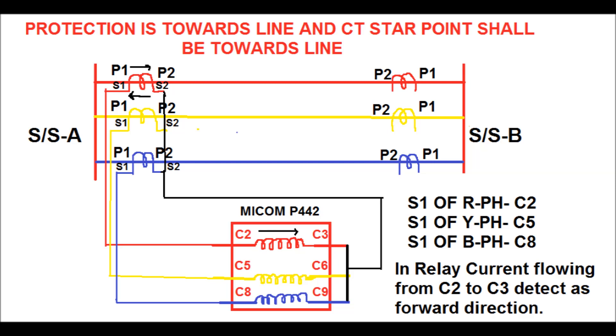For reverse polarity, we can change the polarity either in the primary side or in the secondary side. In the primary side, P2 shall be connected on the bus side and P1 shall be connected on the line side. Alternatively, keeping the primary side unchanged — that is, P1 on the bus side and P2 on the line side — we can interchange the S1 and S2 terminals in the secondary side: S2 shall be connected to C2 and S1 shall be connected to C3. This is how the polarity can be reversed for a CT.